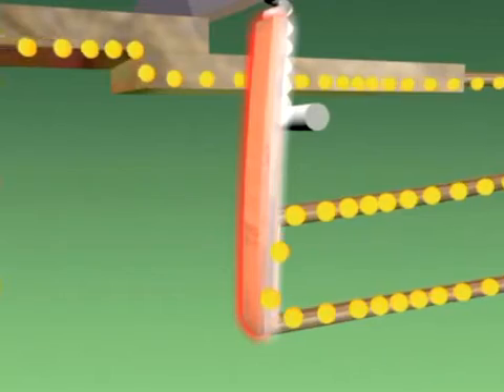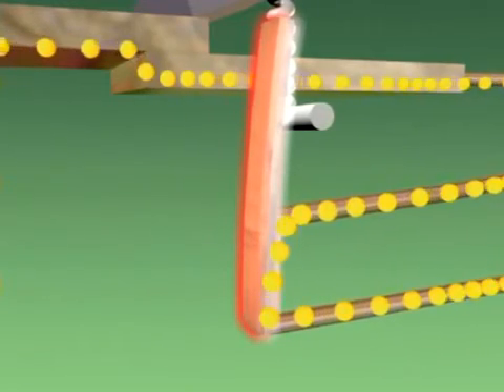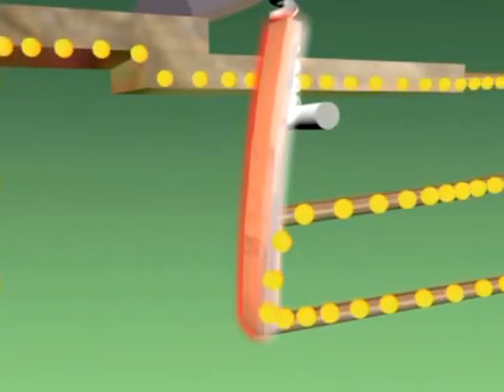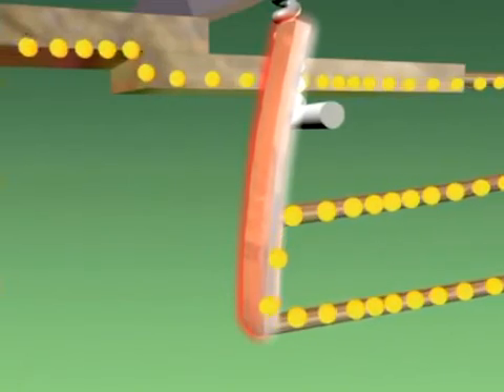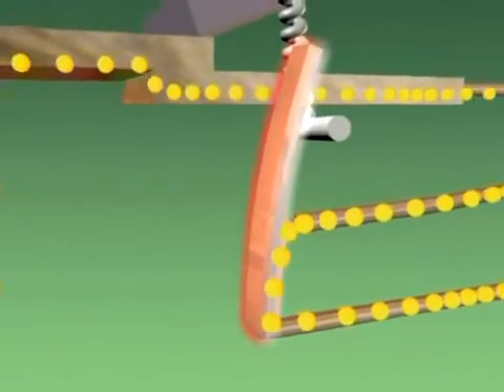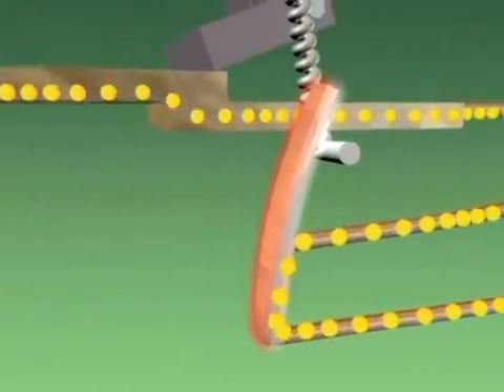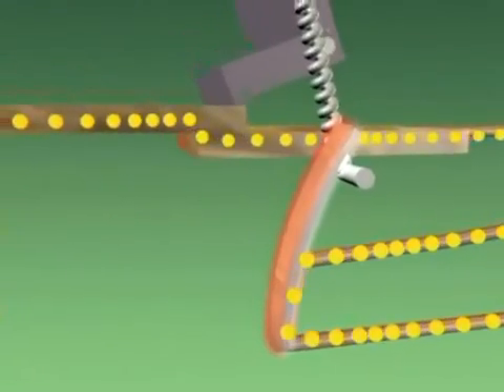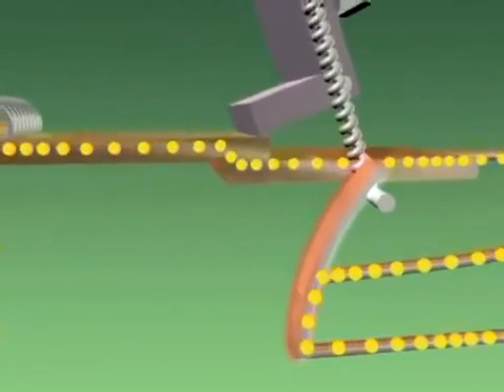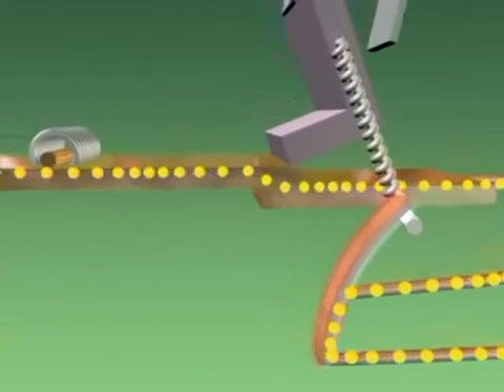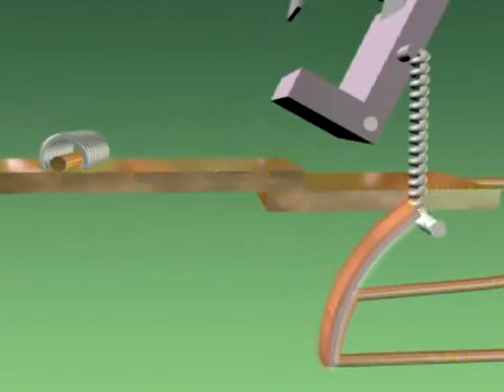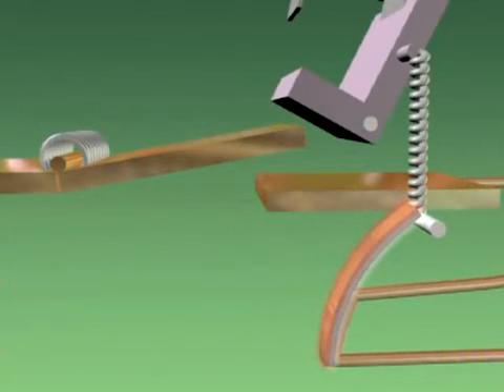As it bends, it begins to force the spring of the lock mechanism towards the point where the lock will snap open. When the current carrying capacity of the circuit breaker is exceeded, the bending bimetal strip forces the spring far enough to snap the lock open. In turn, the switch is released and itself snaps back to quickly and cleanly break the circuit.